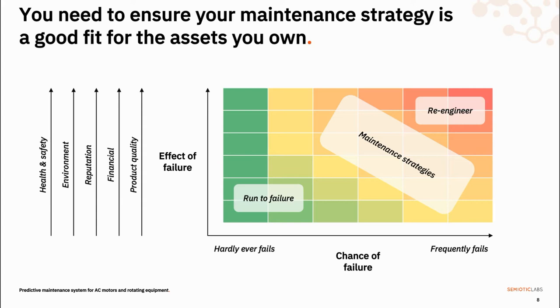For instance, if a pump fails on average every 10 years and you want to achieve 95 percent availability, you can calculate the optimal time to replace that class of pumps by analyzing the normal distribution of failures. What this means is that you'll likely have to replace these pumps every, say, five years, because 95 percent of your pumps will not fail in those first five years. But it also means you're replacing many pumps that have a good five to ten or even more years left in them, which is wasteful in terms of both the environment and efficiency.